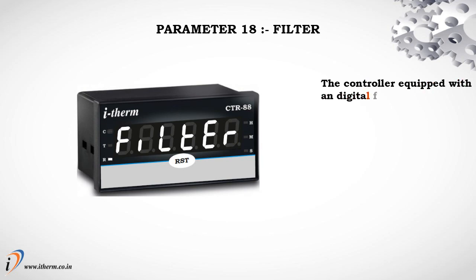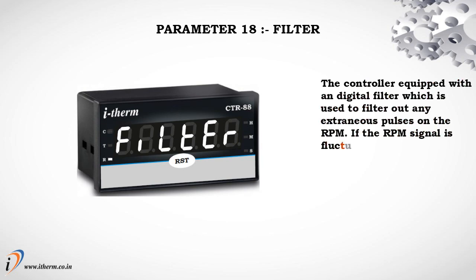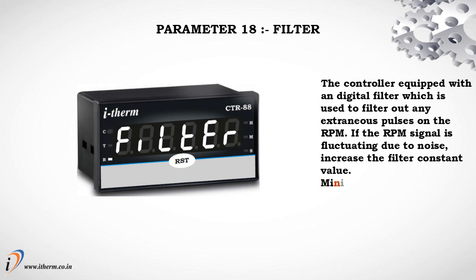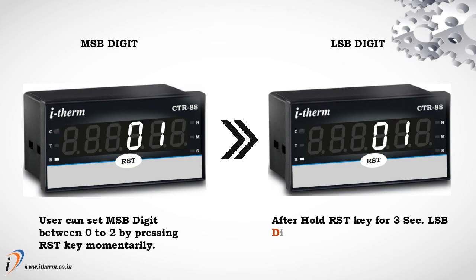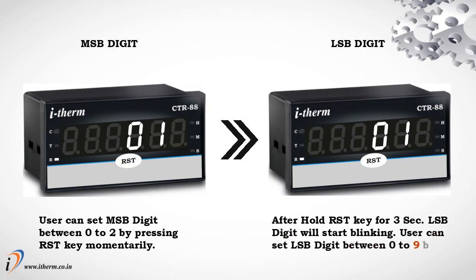Parameter 18: filter. The controller is equipped with a digital filter used to filter out any extraneous pulses on the RPM signal. If the RPM signal is fluctuating due to noise, increase the filter constant value. Minimum filter value equals 1; maximum filter value equals 20. The user can set the MSB digit between 0 to 2 by pressing the reset key momentarily. After holding the reset key for 3 seconds, the LSB digit will start blinking; the user can set the LSB digit between 0 to 9 by pressing the reset key momentarily.